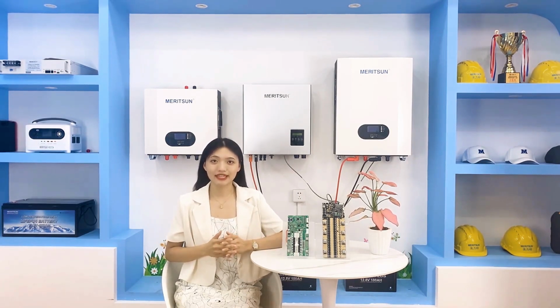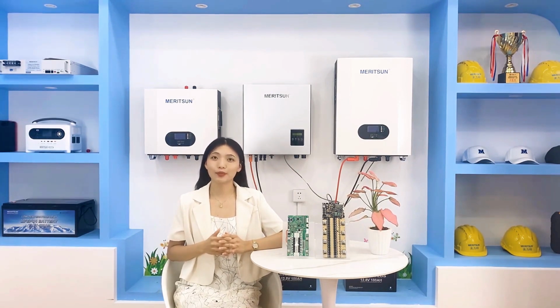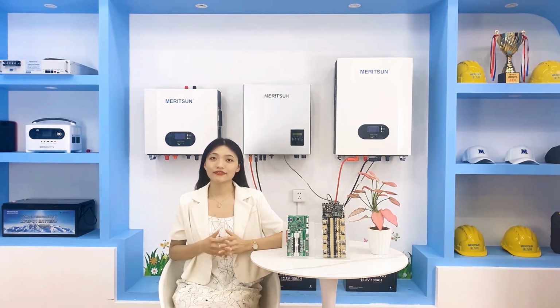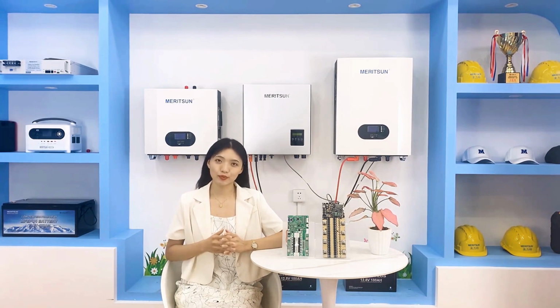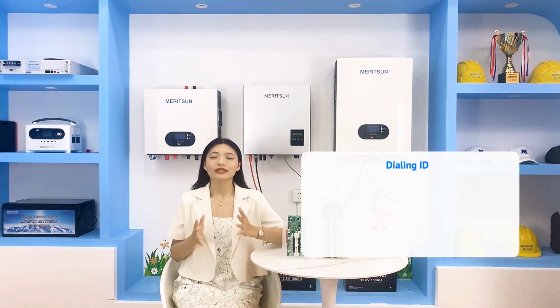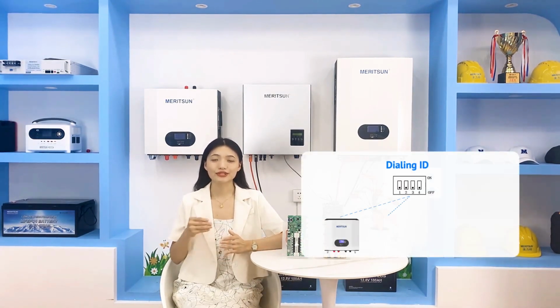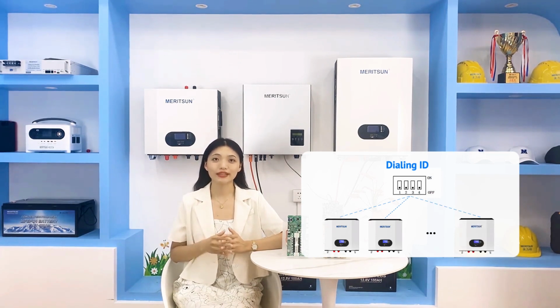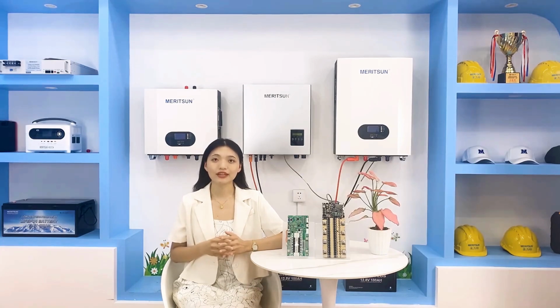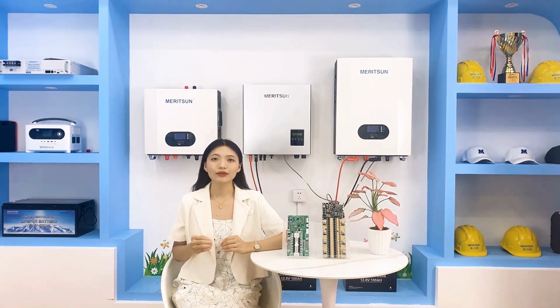Secondly, we should also pay attention to the dialing code on the hardware part, which is almost the most intuitive of all factors. If you can correctly understand the definition of dialing the code, then you will be more handy. First of all, the purpose of dialing the code is to assign an ID to each battery, which is similar to our ID card. In the management of the entire battery system, it must know which battery a signal comes from. That's why we need to assign an ID to the battery.